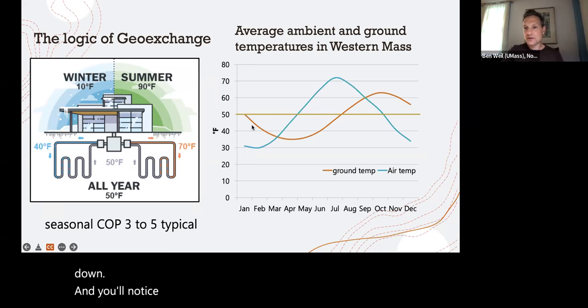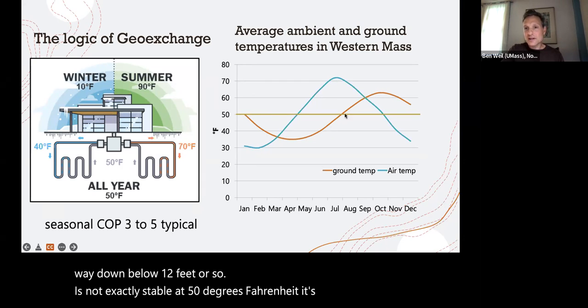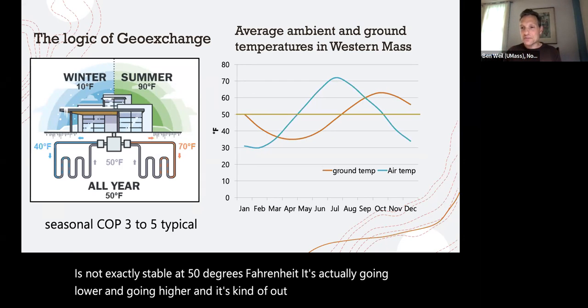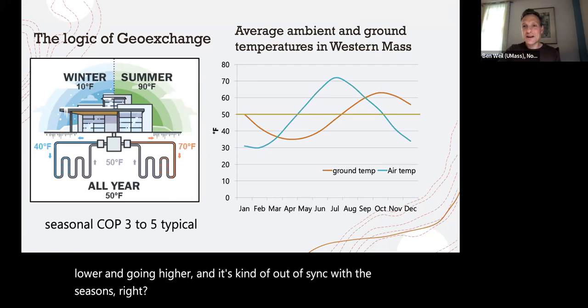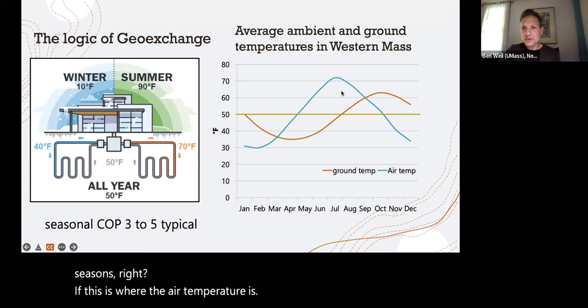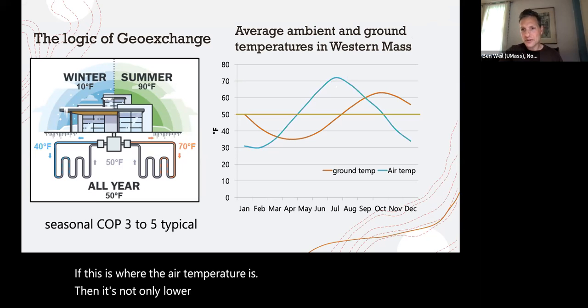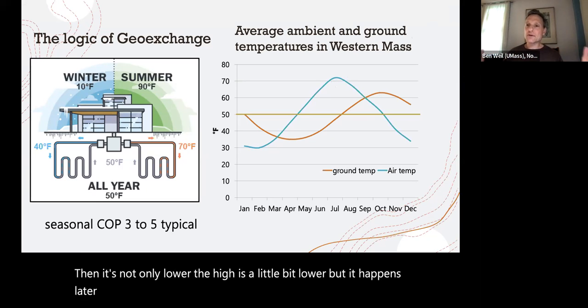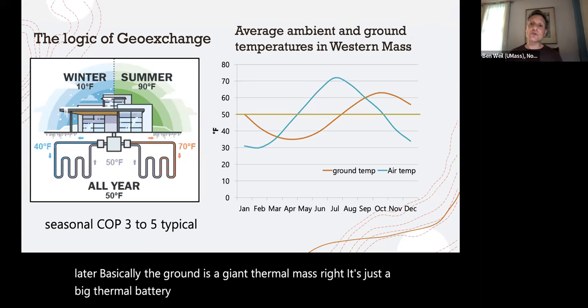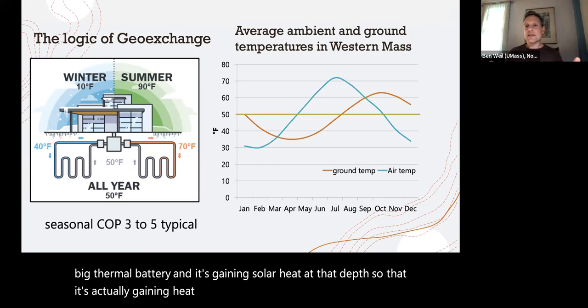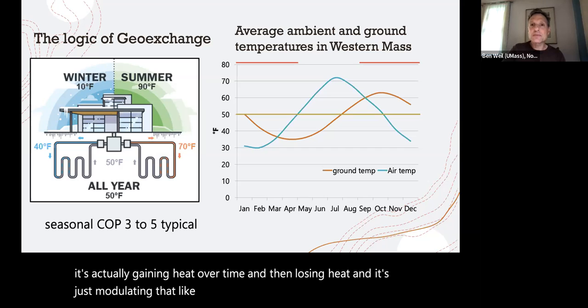And you'll notice that when it's not all the way down below 12 feet or so, the ground temperature is not exactly stable at 50 degrees Fahrenheit. It's actually going lower and higher, and it's out of sync with the seasons. If this is where the air temperature is, then the ground's high is a little bit lower, and it happens later. Basically, the ground is a giant thermal mass. It's just a big thermal battery, gaining solar heat at that depth, so it's gaining heat over time and then losing heat. And it's just modulating that like a thermal mass.